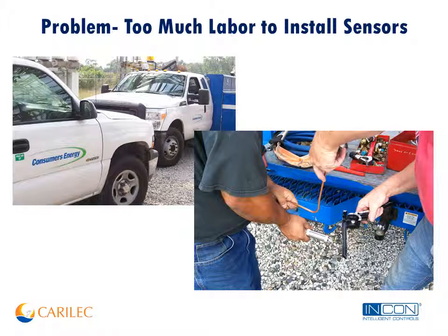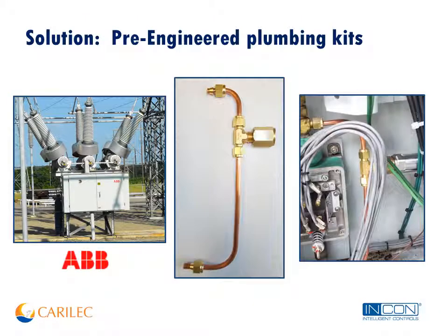Utilities are wary of monitors and other devices that require a lot of labor to install. And yes, if these things aren't thought out in advance, it can take a lot of labor, but we've brought all our experience to bear to provide pre-engineered kits that help you install these things in under 2 hours per breaker.